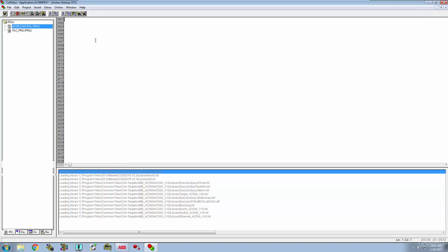And now what needs to happen in startup? Well, this is where we're warming up. So we need to fill our tank and make sure that it's in the appropriate level range. And then we also need to heat our tank up and make sure that the temperature is where we want it as well. And the other thing that we need to do is once the temperature gets up to 300, we can start our mixer, and our mixer has to be running for at least 30 seconds before we can transition out of here and go into operation.